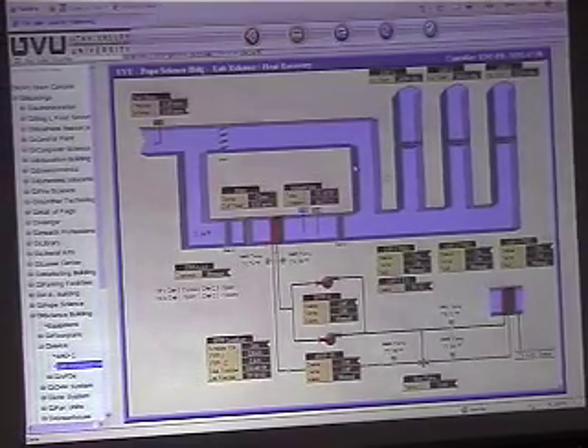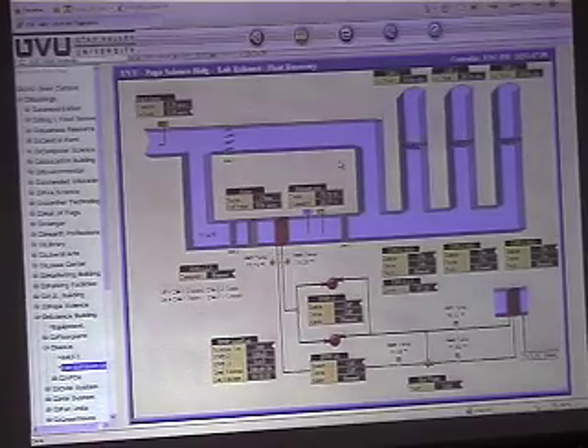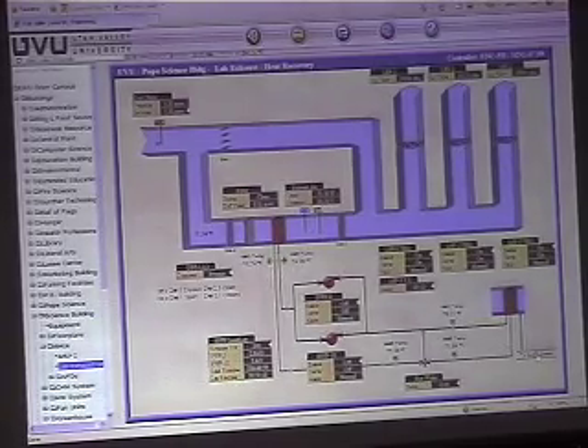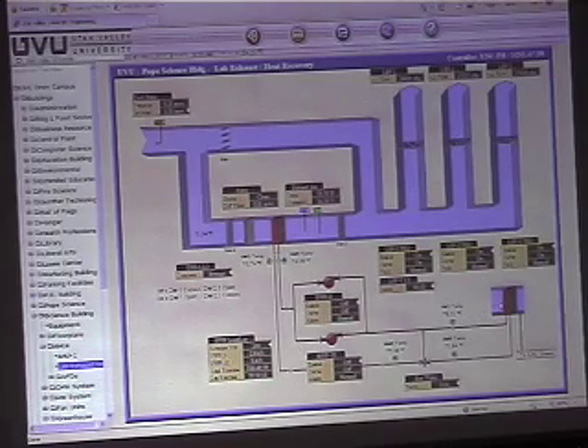Any questions on this portion here? On the transfer from that coil there to there, how much heat, or what temperature, do you anticipate that loop being, like in January? I don't know, we didn't have it up and going when it was super cold outside. By the time we got the unit up and running, our January was pretty mild, so we weren't seeing sub-freezing temperatures outside. But this valve actually didn't even have to be all the way open. I was able to get my 48-degree discharge without reaching its maximum temperature, or its maximum position.